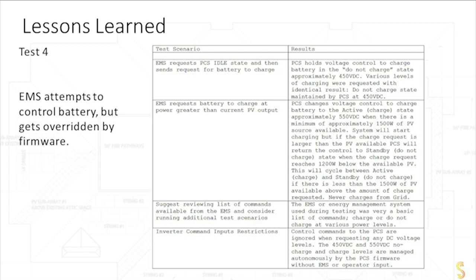So we test this. We test that if the EMS commands the battery to export power, even though it's only operating at 450 volts, that it can't. Or if the battery is at its operating voltage window, that even if we're dangerously close to 0, that red line, if we're exporting power out into the grid, but only a little bit, and the EMS commands the battery to suddenly charge a whole lot from the grid and drive that red line under 0 and start importing grid electrons into the battery, the inverter will take over and say, nope, this firmware in my inverter does not let you do that. This is a hard-coded feature, a hard-coded function. Nobody can tell me otherwise. That's test number 4, and that's very easy to check.